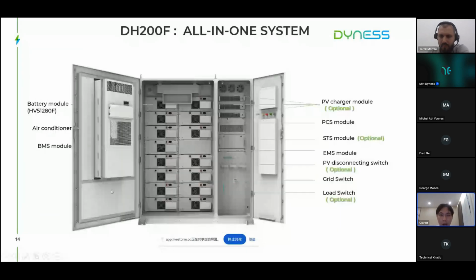We can check the structure here. The left part is the battery side. Inside there can be a maximum of 50 pieces of battery, and this one is the BMS module. This part has a PV charging module and also the PCS, and this one is the STS. The MPPT, the STS, the PV disconnecting switch and the load switch are optional, depending on your need to make it an on-grid, off-grid, or hybrid system.